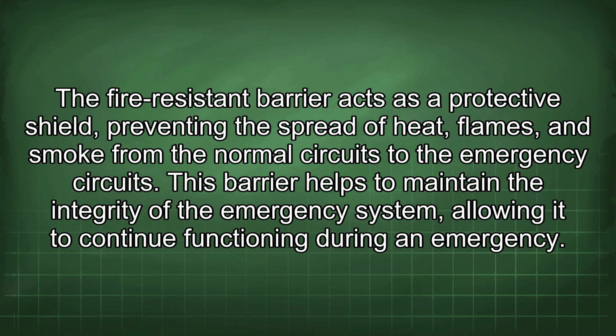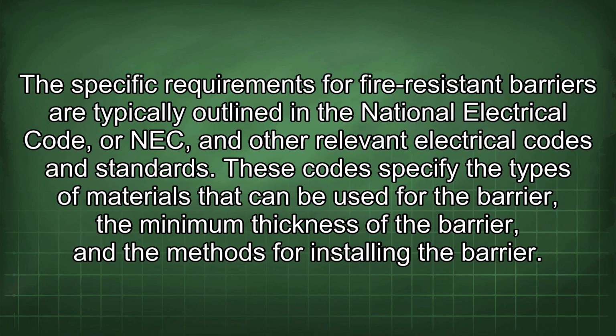The fire-resistant barrier acts as a protective shield, preventing the spread of heat, flames, and smoke from the normal circuits to the emergency circuits. This barrier helps to maintain the integrity of the emergency system, allowing it to continue functioning during an emergency. The specific requirements for fire-resistant barriers are typically outlined in the National Electrical Code, or NEC, and other relevant electrical codes and standards. These codes specify the types of materials that can be used for the barrier, the minimum thickness of the barrier, and the methods for installing the barrier.